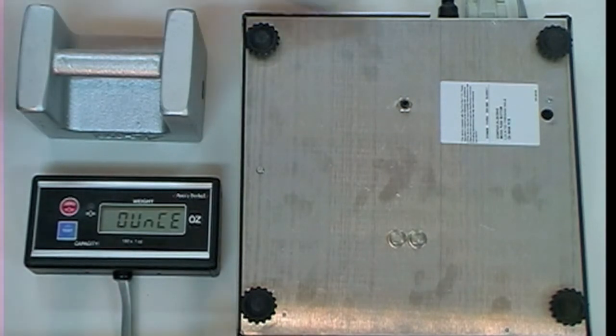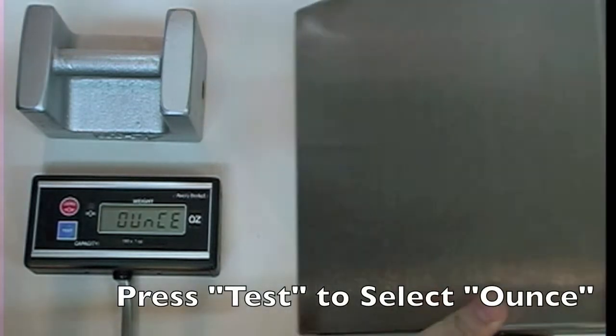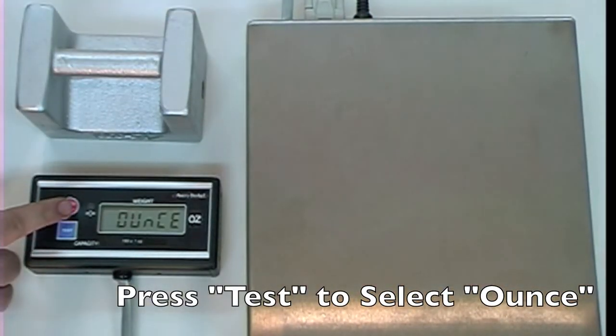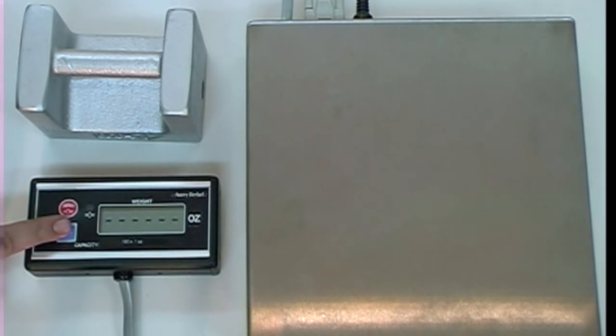We now need to choose the unit of measure we want to calibrate for. In this case, we need to choose OUNCE. Press the red zero button until OUNCE is displayed on the screen, then select it using the blue TEST button.